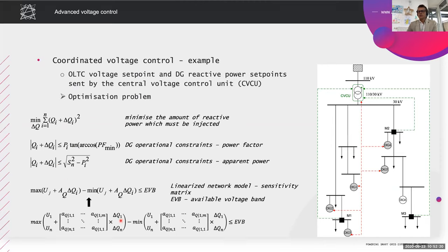And these two equations help you to calculate the impact of the reactive power change on the voltage in a particular network node. You heard about this in the presentation before from Professor Strunz. So it's the so-called sensitivity matrix. This is this one. And this sensitivity matrix gives you the information on how much the injection of reactive power in node one will affect the voltage in node two. And by using these equations, you are able to activate the distributed generators which will have the most impact on the problematic network node. In this way, you can optimize the required reactive power generation to maintain the voltages within the defined limits.